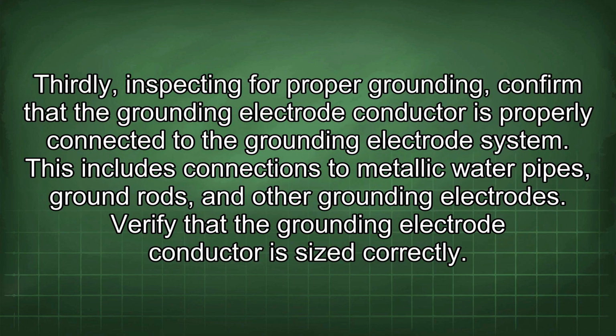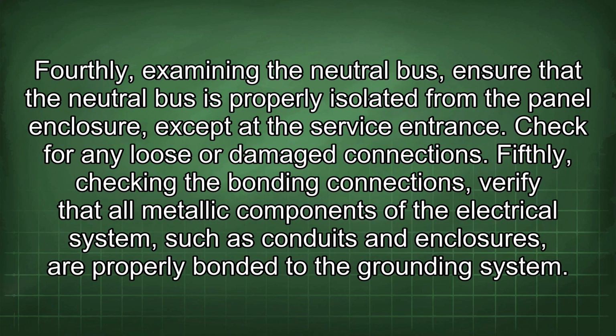Thirdly, inspecting for proper grounding. Confirm that the grounding electrode conductor is properly connected to the grounding electrode system. This includes connections to metallic water pipes, ground rods, and other grounding electrodes. Verify that the grounding electrode conductor is sized correctly. Fourthly, examining the neutral bus. Ensure that the neutral bus is properly isolated from the panel enclosure except at the service entrance. Check for any loose or damaged connections.